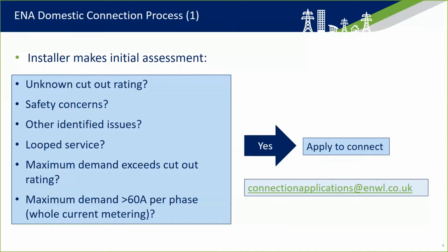Any safety concerns? Are there any obvious signs of damage or burning to the equipment? Any other issues identified? One thing which may be quite common is looped services. This is where a single service cable comes into a property and then continues on to the next door neighbour, and then sometimes the next door neighbour after that. So in effect you've got 2 or 3 properties fed from a single service cable. This was fine for gas heated houses with a relatively low demand, but as soon as we begin adding quite high loads, such as an electric vehicle, it's unsuitable, and our policy is to remove that loop.